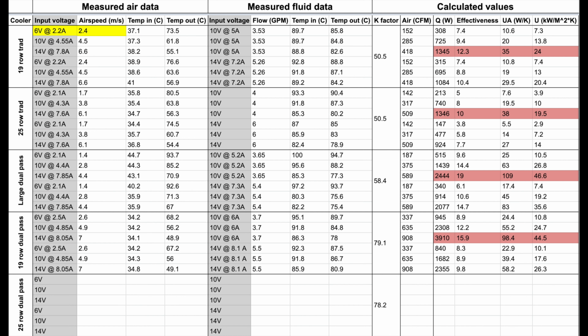There was some variance on it, so we just watched it to see where it mostly was hanging out. We measured a 2.4 meters per second air velocity across the face of the heat exchanger, and then we move over here, we see we have our input voltage to the pump, which was 10 volts. It pulled 5 amps almost on the dot, and we got 3.53 gallons per minute measured.